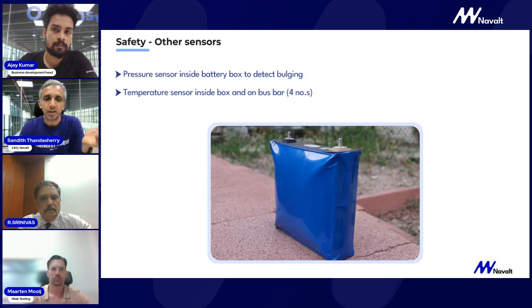In addition to all the class requirements, there are certain things we do based on our experience. We try to put all alarms and safety indications into three groups. One is an information level, where you're made aware something is about to happen. The second causes a slowdown in the system, like the motor being forced to slow down because a parameter such as current or temperature is breached. The third is shutdown, where the system is forced to shut down completely.